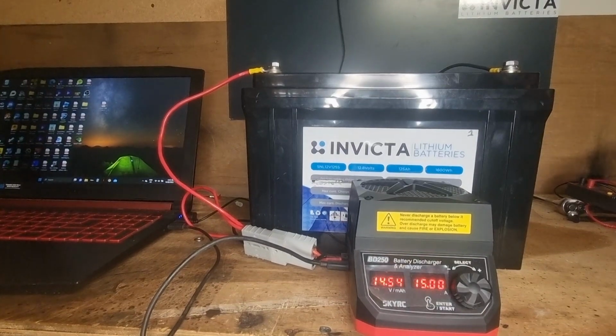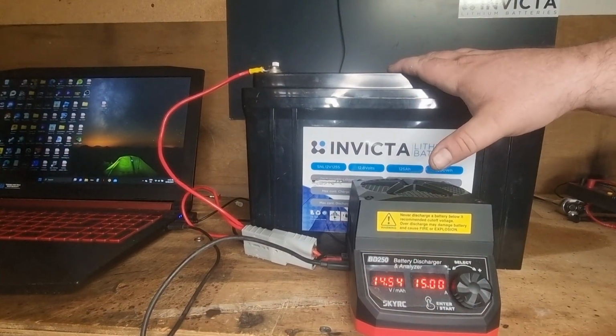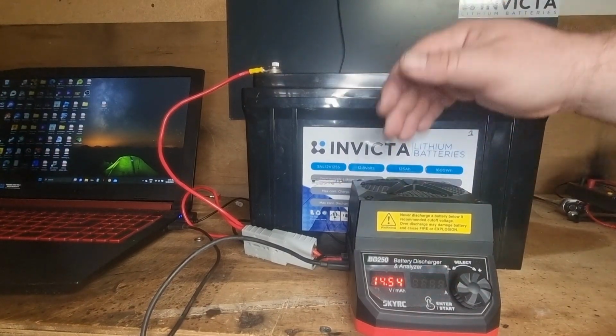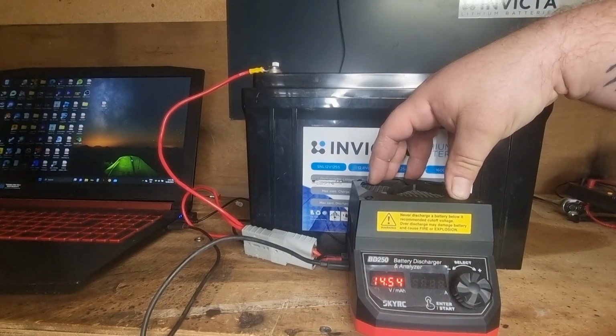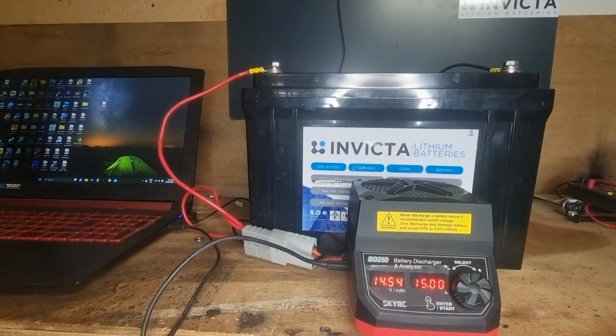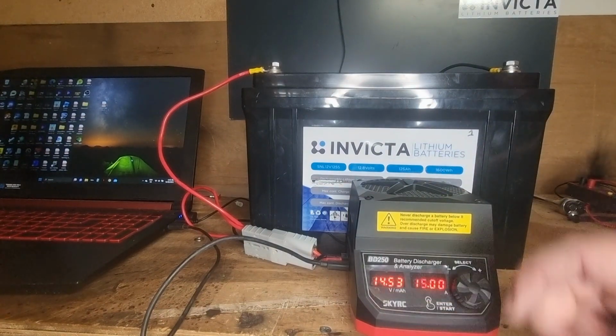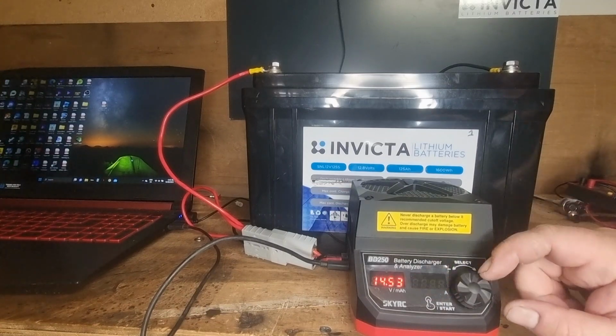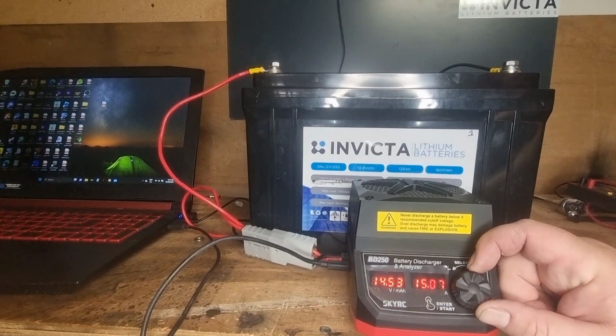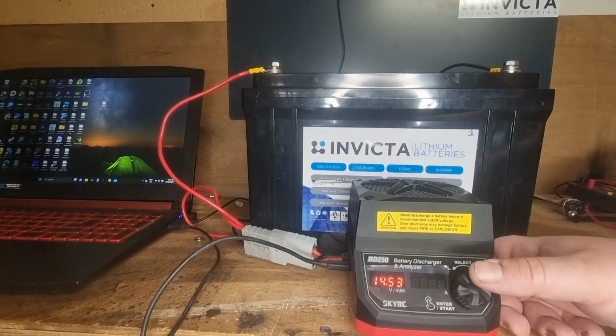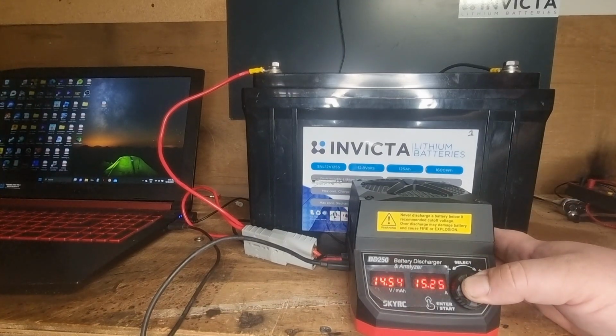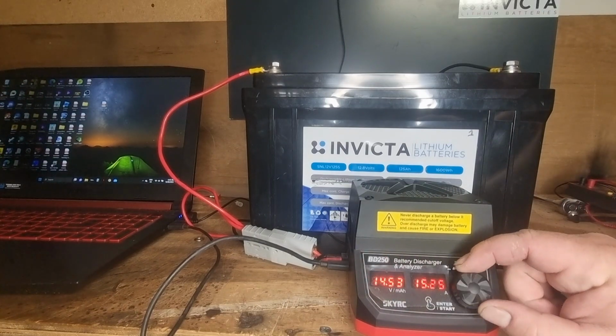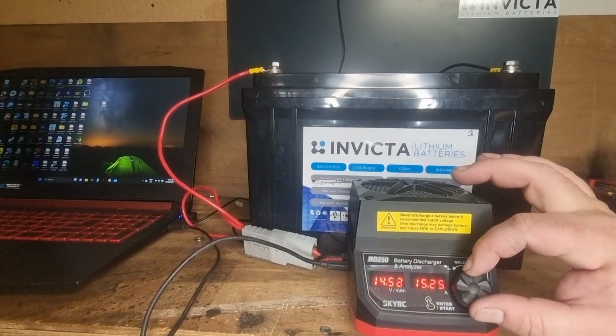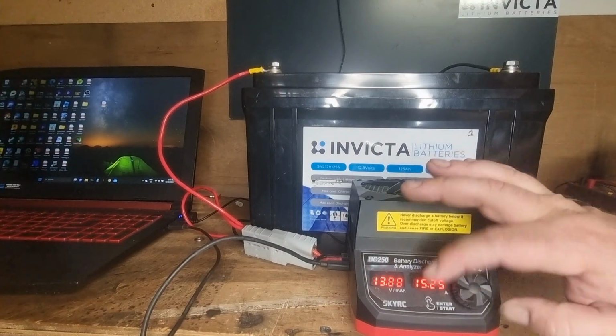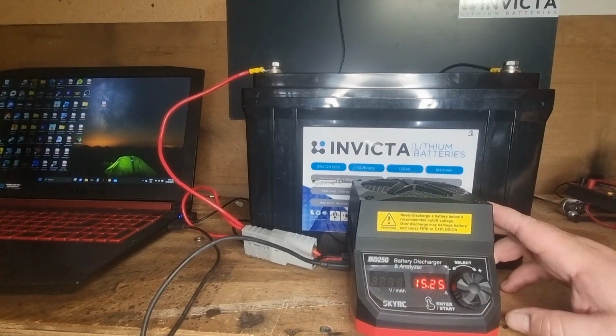Okay, so she is fully charged, so we're going to do a discharge test. Today I'm using the Sky RC BD250. There's a software program on Windows that I'm using, but you can also use these dials here. This is the flashing mode, so you've got your up and down to change how many amps are coming out of the battery—15, you can go right on up, I think 35 might be the maximum, I'll check on the computer. Then you'd tap that in. It's done because there's nothing hooked up. You've also got the voltage of the battery, but it's reading what the voltage of that one is, so that's why it's at 14. This is your discharge down to 10 volts, so you go all the way down. But again, I'm going to use the program on the computer, and I'll show you how to do that now.